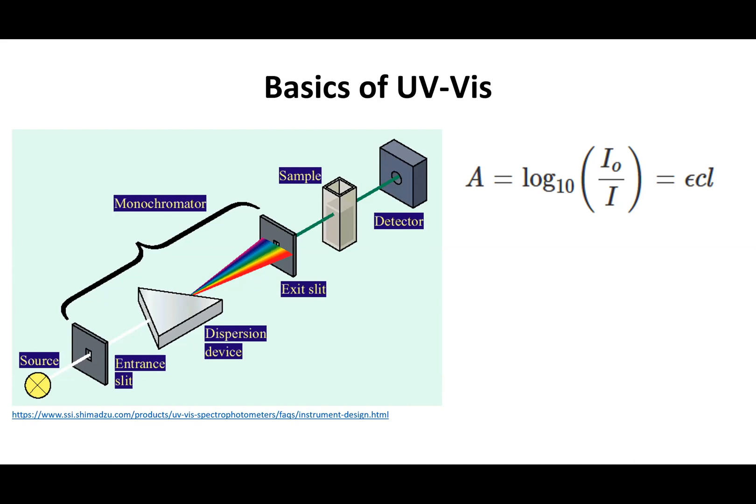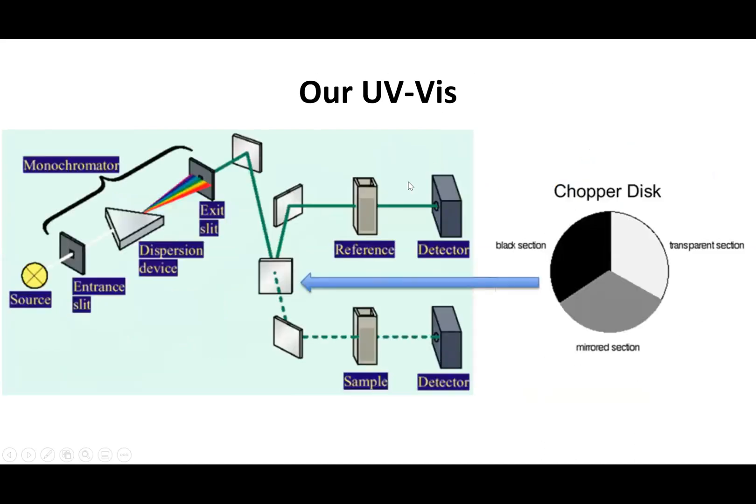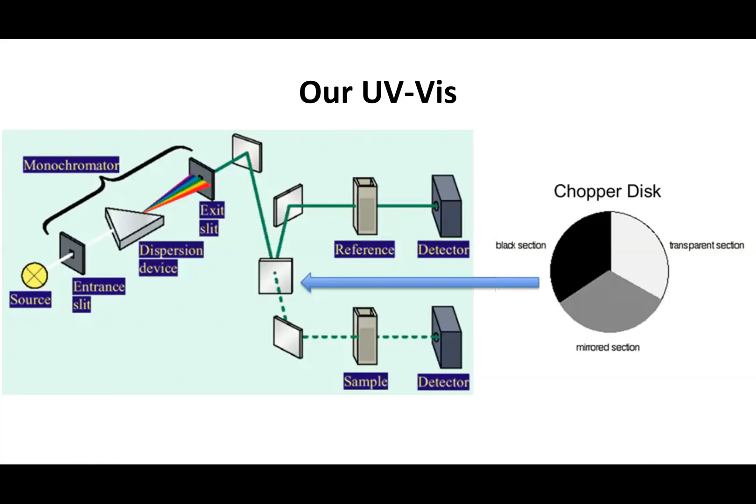The one that we have in our lab actually has a beam splitter in order to have light pass through the sample as well as through a reference slot. That's how you can take the ratio of the incident light going through the reference cuvette in comparison to the sample cuvette at the bottom.